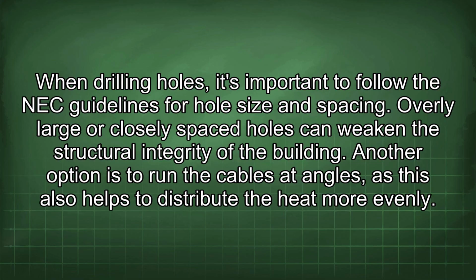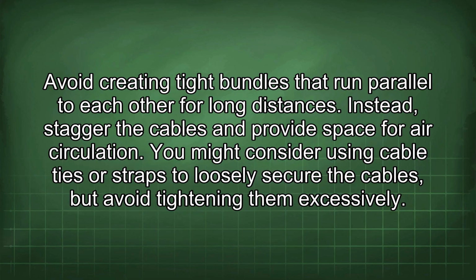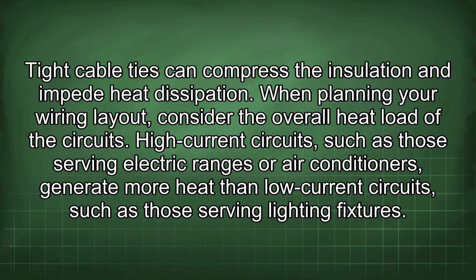Another option is to run the cables at angles, as this also helps to distribute the heat more evenly. Avoid creating tight bundles that run parallel to each other for long distances. Instead, stagger the cables and provide space for air circulation. You might consider using cable ties or straps to loosely secure the cables, but avoid tightening them excessively. Tight cable ties can compress the insulation and impede heat dissipation.